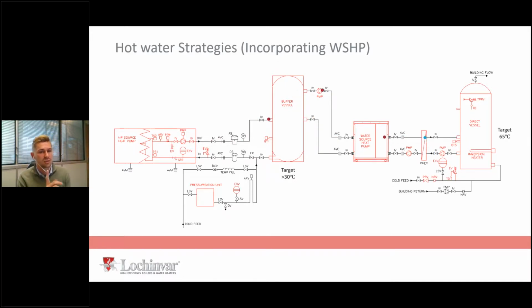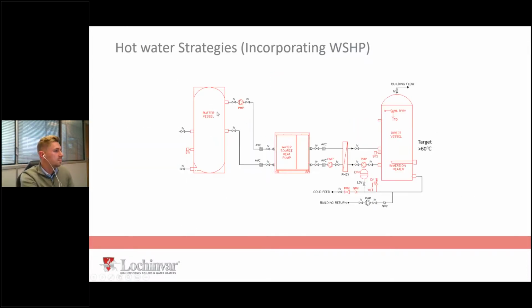You just have to be conscious that you need to calculate and store your peak, because the water source heat pump won't be able to operate instantaneously like a lot of these places already will. So you just got to be aware that if you're expecting to use 10,000 litres of water in a 15-minute period, it needs to be sat there ready for the next time that happens. But to be honest, by far our most popular schematic is this one.